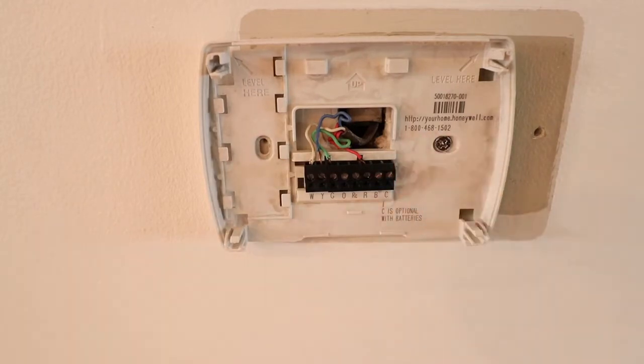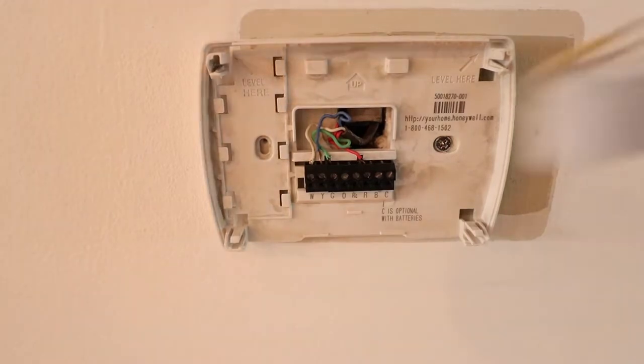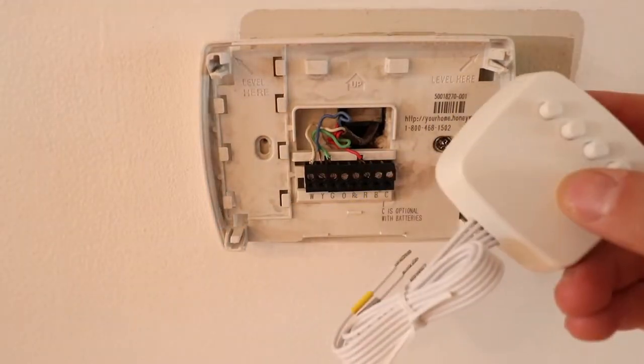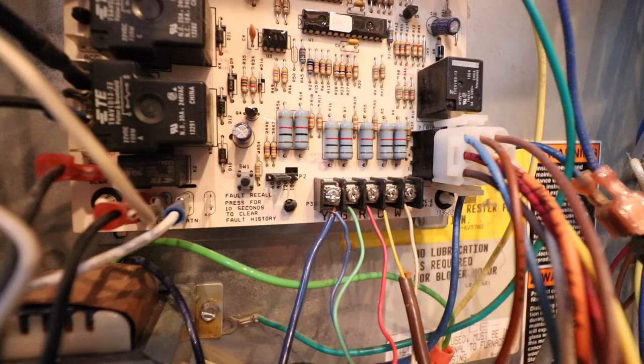That means we're going to need to go to our HVAC system and install this common wire adapter. But pause for one moment—before you get started working on your HVAC control board, I want you to take a picture of the inside where the wires are wired to the control board terminals. This can be very helpful if you have any issues, so you don't forget what your existing wiring looked like, or if you need to restore it to the original configuration.